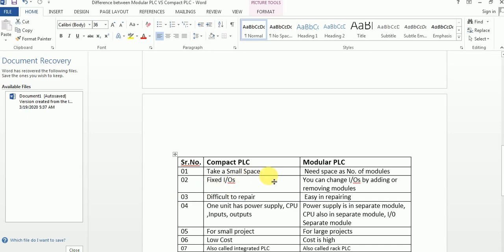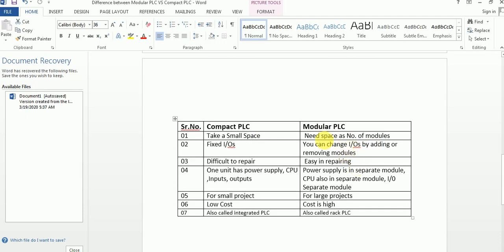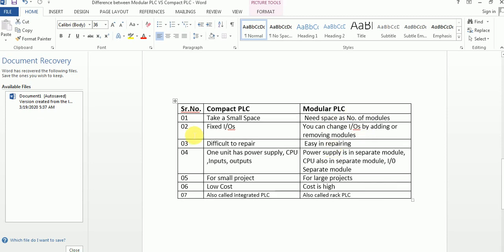Compact PLC takes very small space, but modular PLC takes space according to the size of your project and materials. Also, compact PLC has fixed IOs — in one unit there are fixed inputs like 12, 14, or 30, and the outputs are also fixed values.